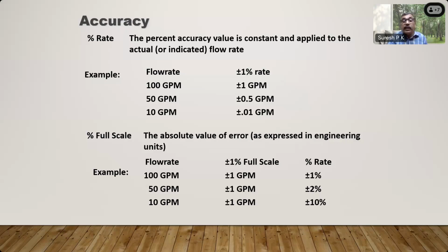If you're stating it as percentage full scale, then at 100 GPM, the specification of the flow meter is stated as 1% of full scale. That is, at 100 GPM it will give 1% error. At 50 GPM, it is again the 1 GPM error, which is 2%. At 10 GPM, it is again giving 1 GPM, which is 10% error. So percentage full scale is something like a misguiding term, and we have to be careful while selecting the flow meter.